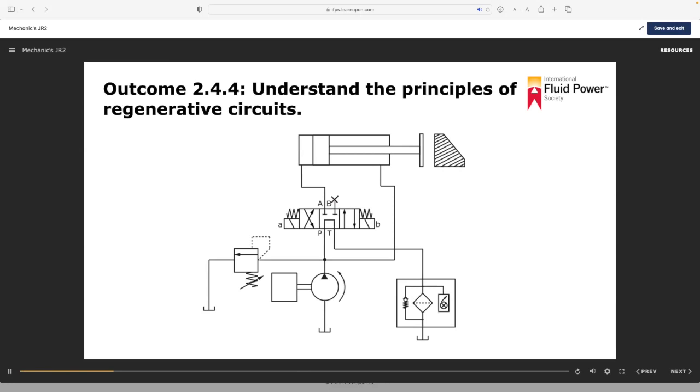into the pressure line. The exhausting fluid is reused or regenerated to do work. Interjecting the exhausting fluid into the pressure line adds a resistive load to the actuator, so that the increase in available flow results in a decrease in available force.